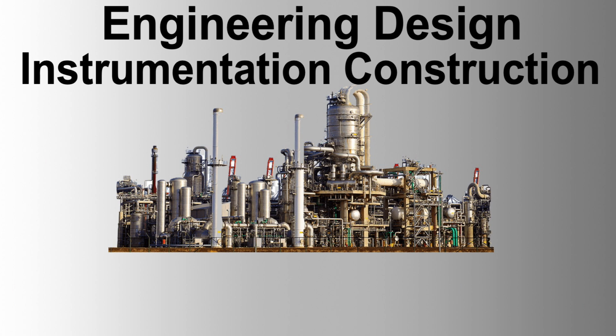Where tubing is installed in a horizontal run, ensure that the fall of the tubing is in the correct way and at the recommended degree of incline. Tubing installed onto galvanized tray shall be supported along its whole length with proprietary molded PCP or similar material blocks of the correct size and fixed to the tray with compatible material nuts, bolts, and washers. The spacing between blocks shall be 1.0 meters maximum.